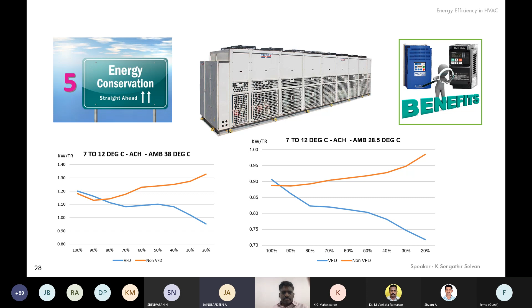You can see this left side chart, where non-VFD chillers are slightly efficient at 100% load, but after 80% load they are hugely inefficient. The y-axis shows kilowatt per TR, the specific energy consumption for this air-cooled chiller. Per TR, at 100% load, it will take around 1.2 kilowatt per TR for Chennai conditions. This one we have taken for 38 degrees, which is the average peak temperature that we have considered.